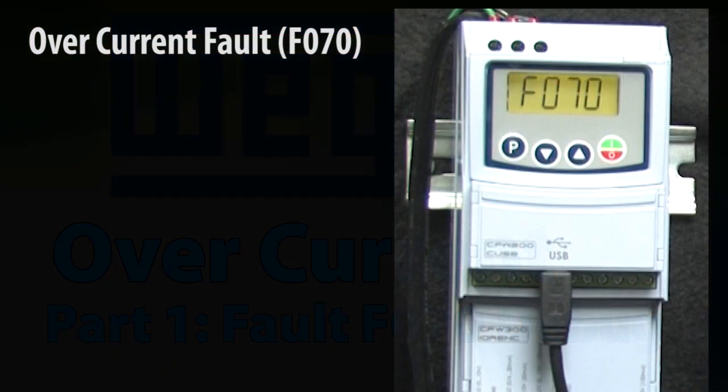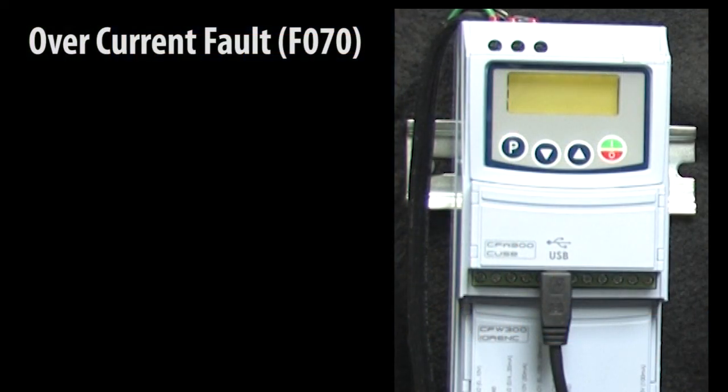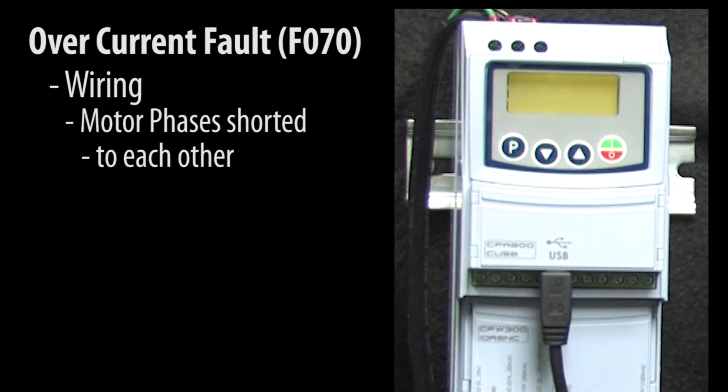There are a couple things that can cause an overcurrent fault. The most common cause is wiring—either two or more motor phases are shorted together, or a motor phase is shorted to ground.